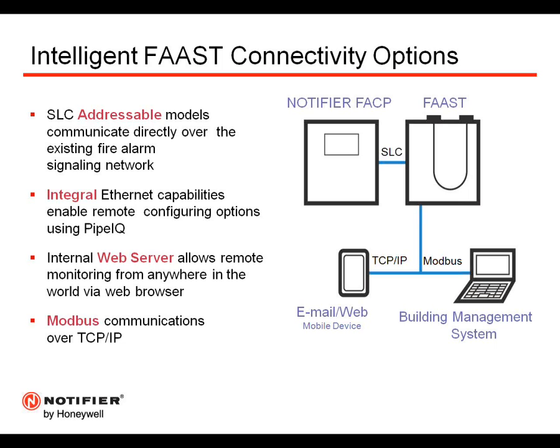This also enables us to send out email communications for all fire and trouble events. FAAST also communicates the Modbus TCP IP protocol through that same Ethernet port, and these are all available standard out of the box on the FAAST detector.